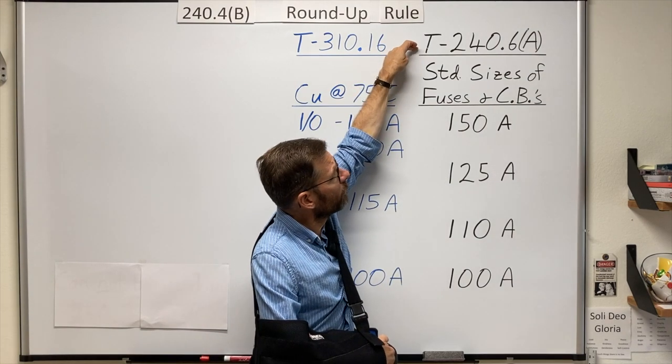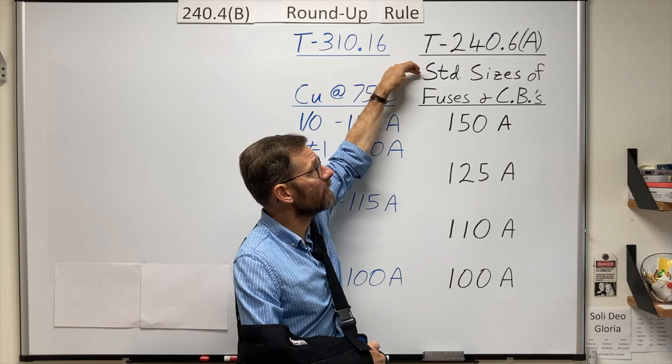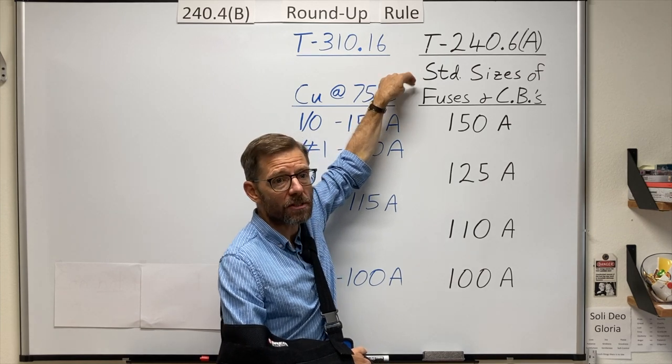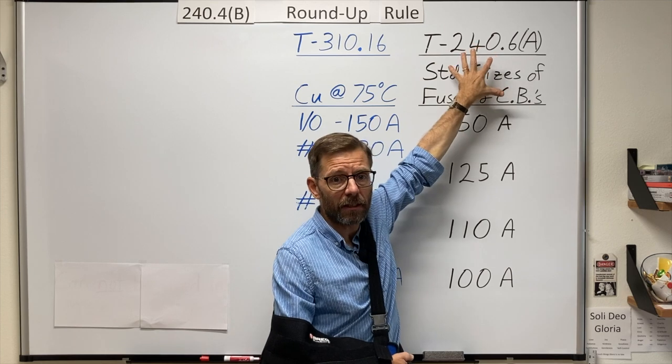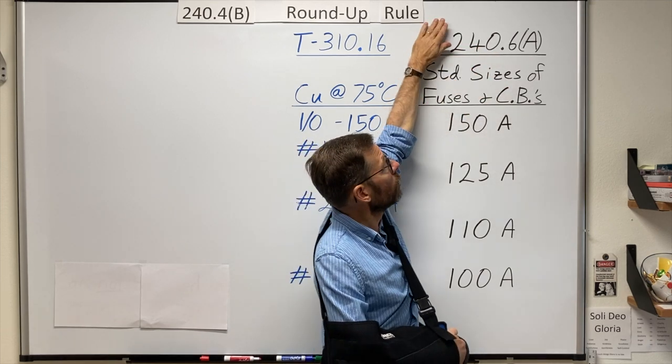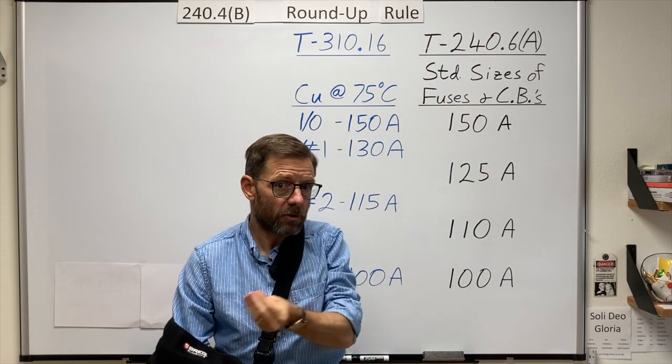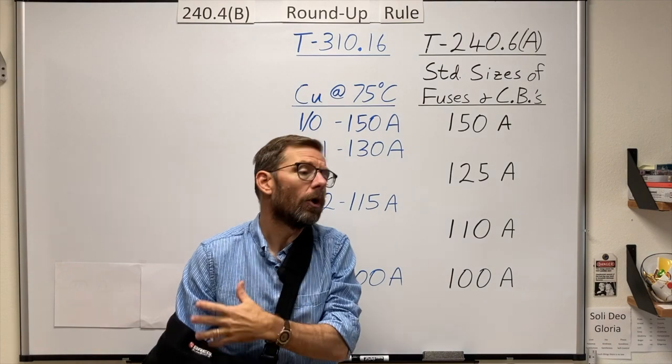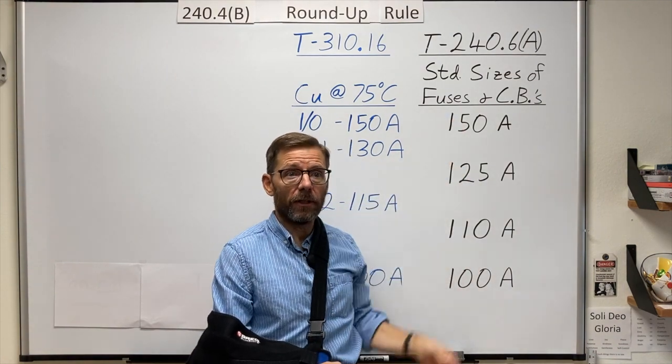And over here, from Table 240.6a, I have the NEC-dictated standard sizes of fuses and circuit breakers. It doesn't state it specifically, but they're for 1,000 volts and less. And also, in the written section, it states that I can use non-standard sizes. However, all the rules are based on standard sizes, so that's what I put here.